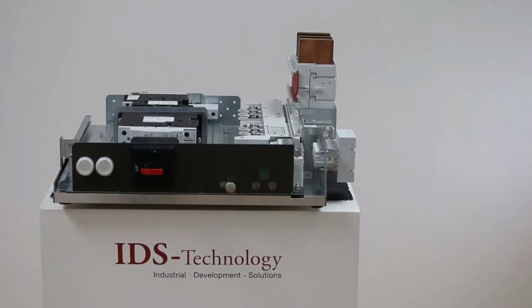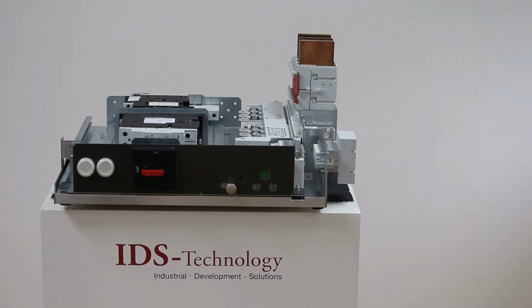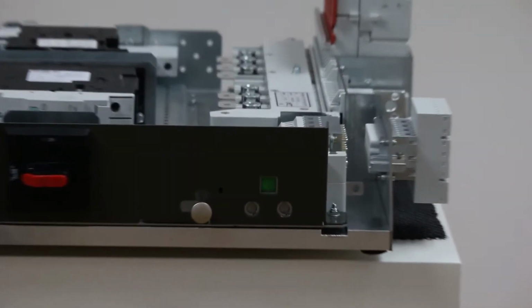The drawer shown here is only 450 mm wide and 75 mm high. The drawer is equipped with electrical switching devices for a motor starter up to 22 kW. This demonstrates an extremely compact and space-effective sample. The drawer is located in its drawer compartment, which will be visible when the drawer is pulled out.